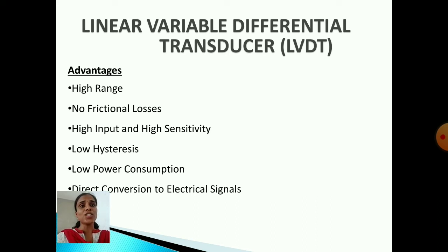First one is high range. Range means the difference between the lowest and the highest value. In LVDT, it has a very high range of measurement of displacement and it can measure in the range from 1.25 mm to 250 mm. Second one is no frictional losses, as the core moves inside a hollow cylinder so there is no loss of displacement and input as frictional loss. So it makes LVDT a more accurate device and it has high input and high sensitivity.